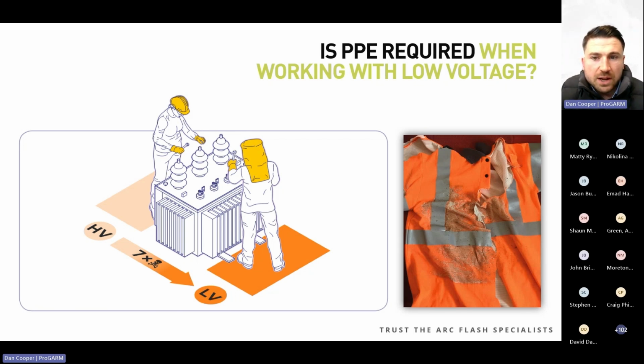Arc flash hazard levels may actually be higher at low voltages due to the high fault currents. And because awareness among some engineers working on low voltage systems is so much lower, the risk to them as individuals could be perceived as greater due to the false sense of security.